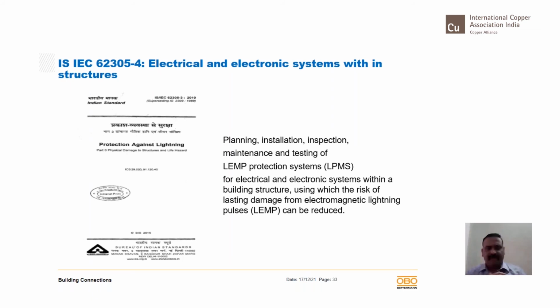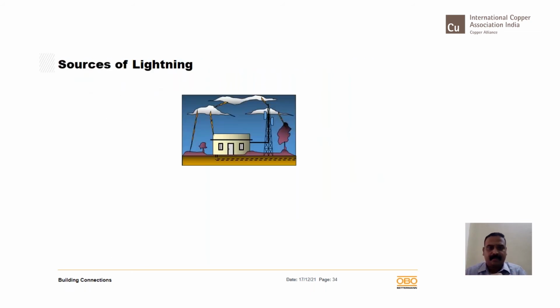Part 4 elaborately talks about the need for LPMS, which is the LEMP protection system, the lightning electromagnetic impulse protection system. It is nothing but a surge protection device. There are several pieces of equipment that we use which are supported by power, voice, data, and communication. When you want to protect all these lines, obviously a device is required at every input, like power input, data input, and voice input, to take care of those separate lines, because these are not associated with your building. These are cables which are coming in externally.